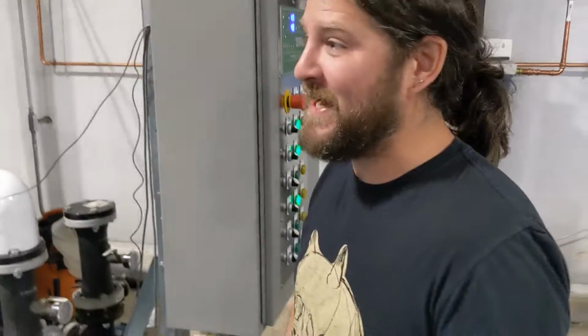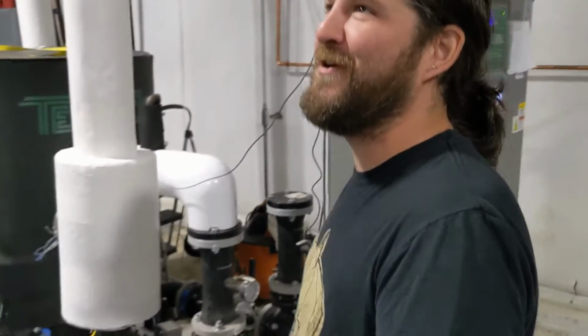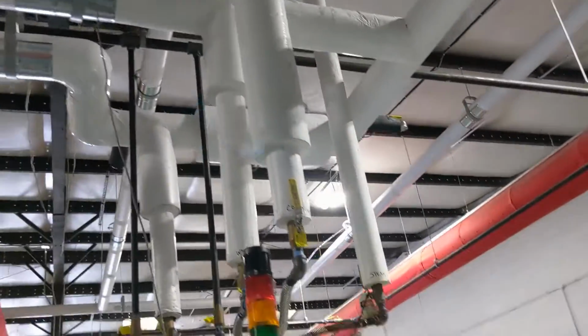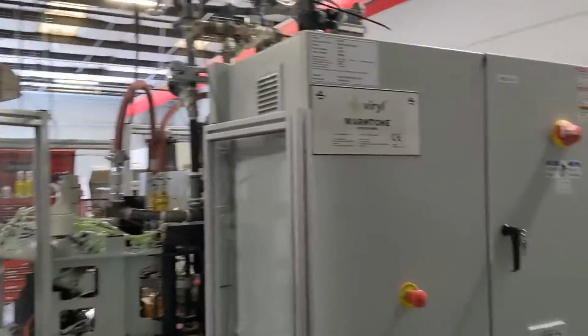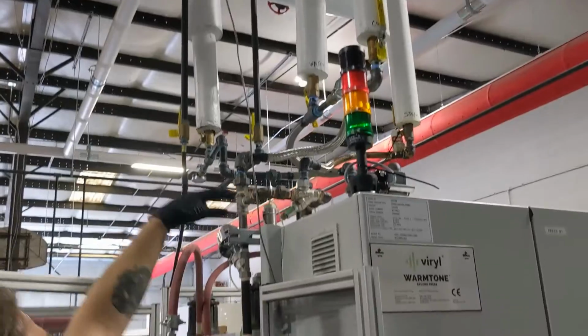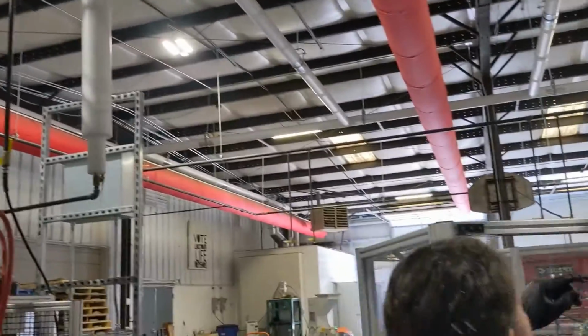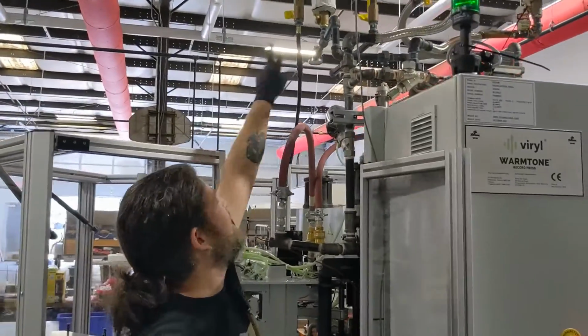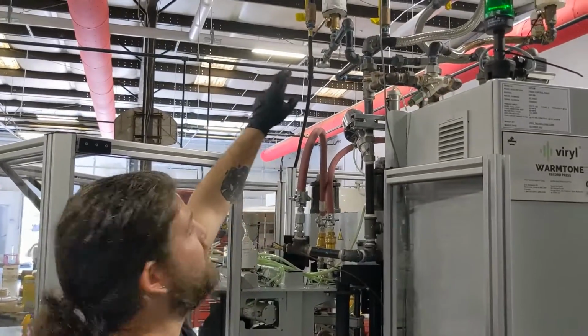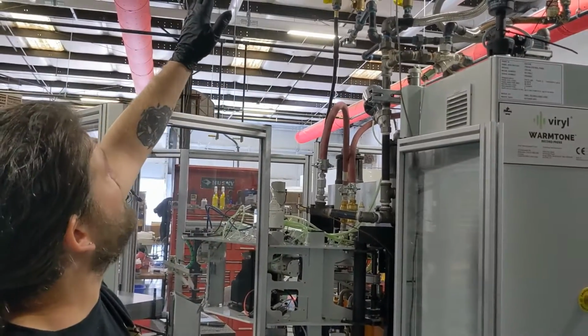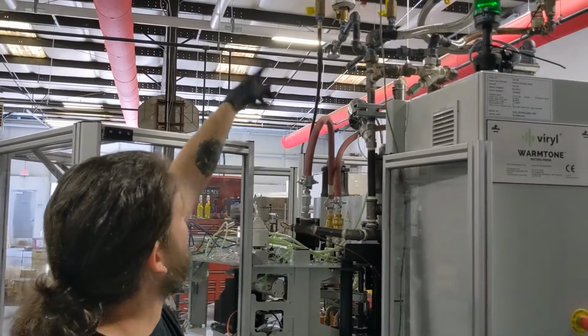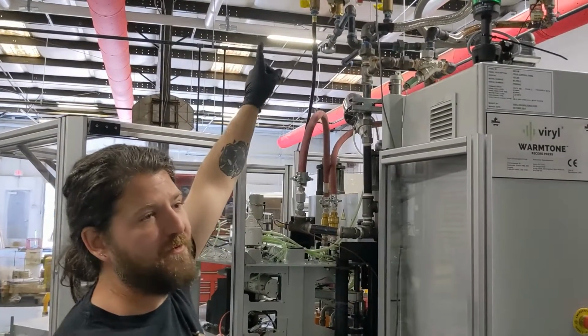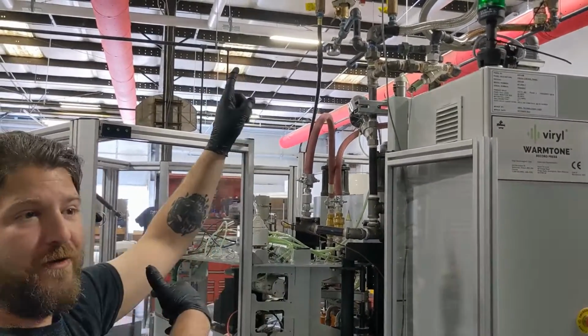Ingenuity. Yeah, you hire all these engineers and all these experts, and I'm the one over here coming up with all the solutions. Same here. When we originally built this chiller loop, this side right here is closest to me. With this drop here, that's where water comes into the press. Same on that one. And on the other side here, that's where water goes out of the press. Originally when the contractors built this, that return pipe ended right at where that pipe goes up. So there was no flow of water in that pipe.